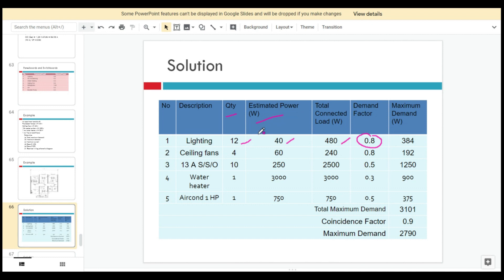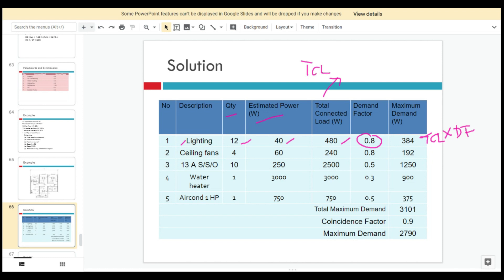For lighting, we assume a demand factor of 0.8, which is 80%. You calculate the maximum demand for lighting as TCL times the demand factor. So for lighting: 12 times 40 watts gives 480 watts TCL, then multiply by 0.8 to get the maximum demand. Then proceed with the ceiling fans: 4 ceiling fans times 60 watts gives 240 watts TCL.